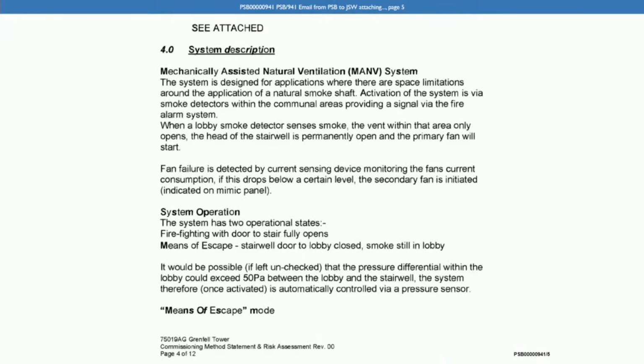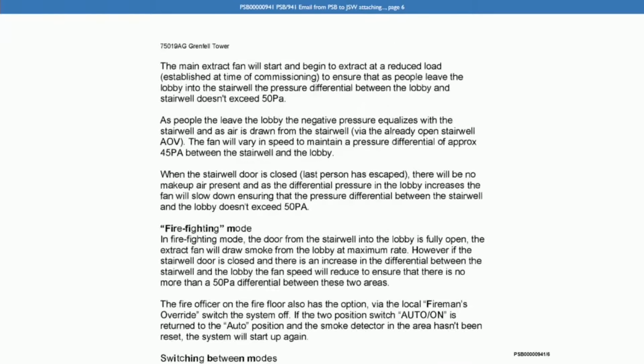Now, let's just turn to the PSB commissioning method statement that we looked at earlier, PSB00000941. That's the method statement that we know you wrote under some time pressure, as you've explained. If we go to page 5 of it, we can see there's a section 4 in the middle of the page called System Description. Then if we go over the page to page 6, if we look at the first 3 paragraphs of that, it says the main extract fan will start and begin to extract at a reduced load to ensure that as people leave the lobby into the stairwell, the pressure differential between the lobby and stairwell doesn't exceed 50 pascals.